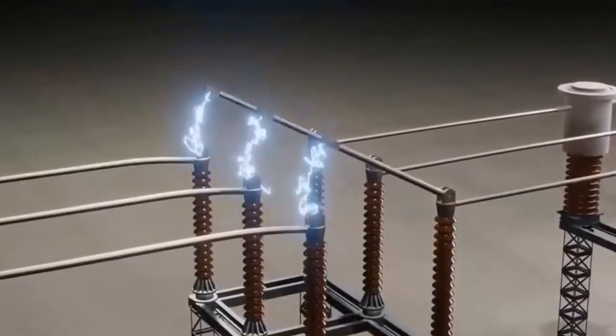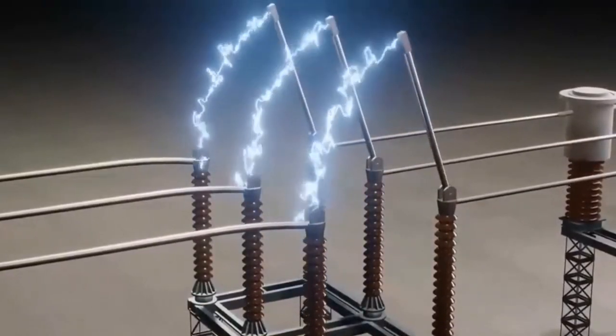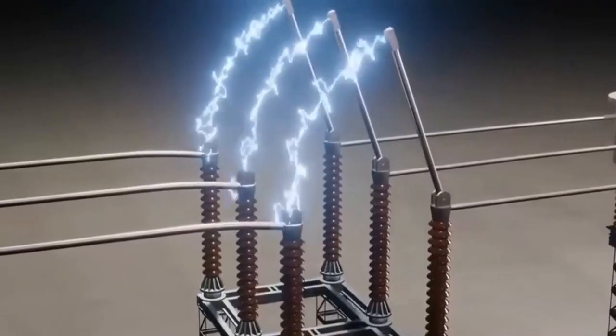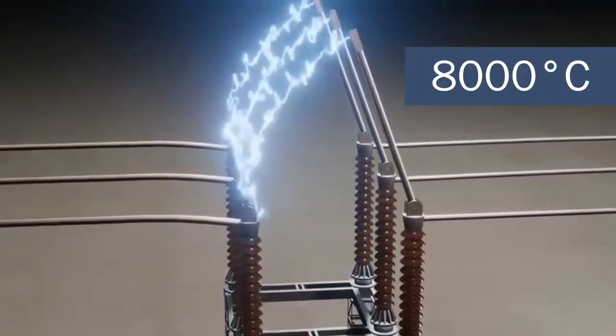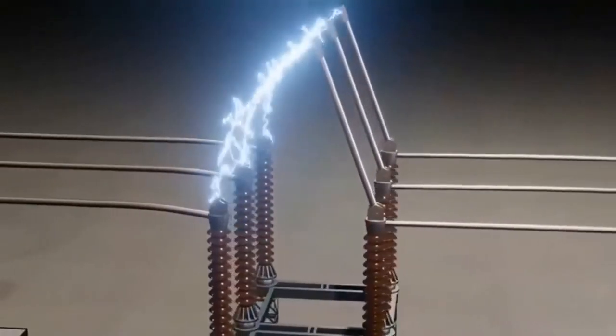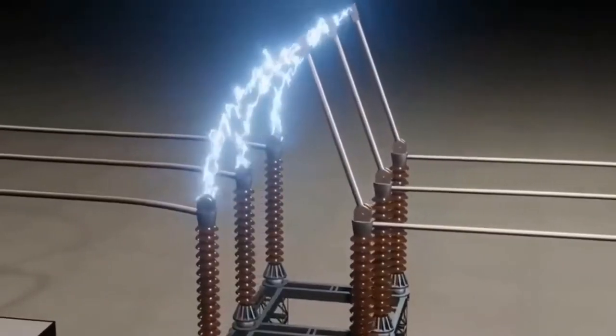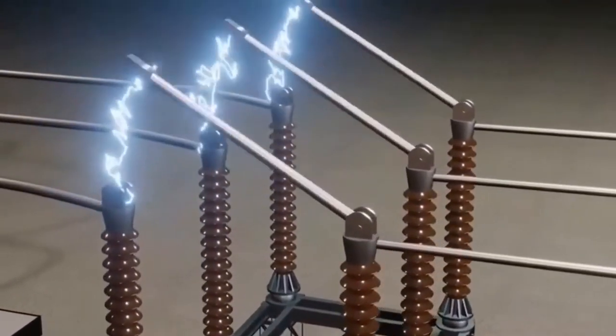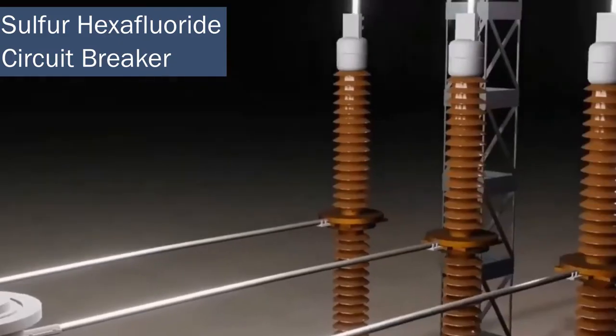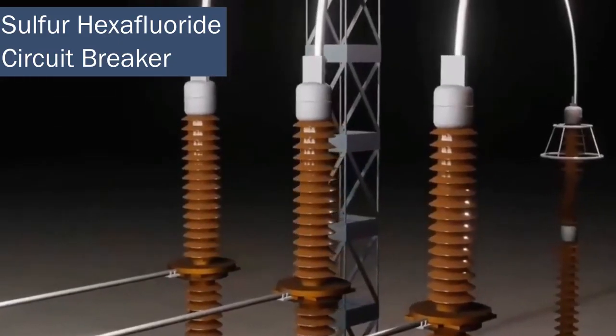If the high voltage circuit is disconnected like this, a long arc will form between the contact points, and the arc temperature can reach 8,000 degrees Celsius, causing the contact points to start melting, and the circuit unable to be completely disconnected. To solve this problem, engineers invented the sulfur hexafluoride circuit breaker. Let's see how it works.